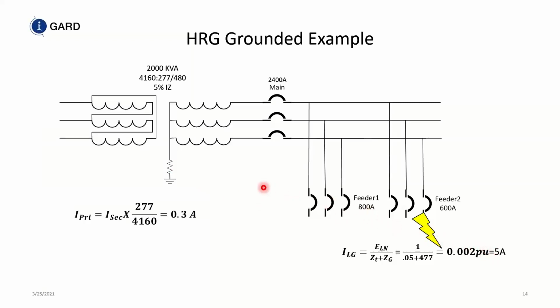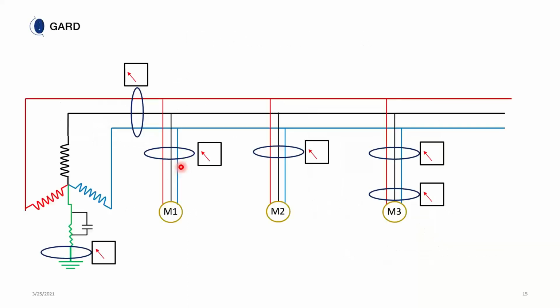If we have a 55 ohm resistor here, we change the fault current to 5 amps. Let's assume we change the value of the resistor to 110 ohms. We change it to 110 ohms, the fault current is now 2.5 amps. Now let's say we do that cyclically. We have a contactor here, and we change the value of this resistor from 55 ohms to 110 ohms, and back to 55 ohms, and we do that cyclically. So for 1 second, there's 55 ohms. For another second, there's 110 ohms. So when we have a fault, we can actually let that fault tell you where it is by locating it.